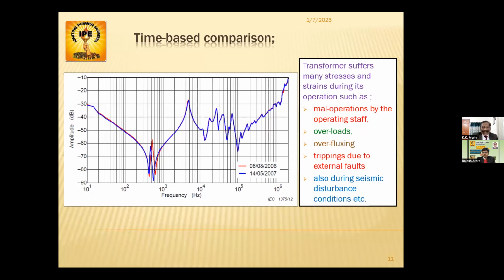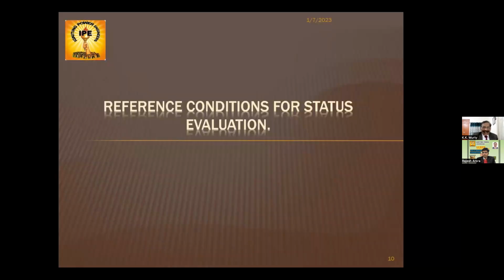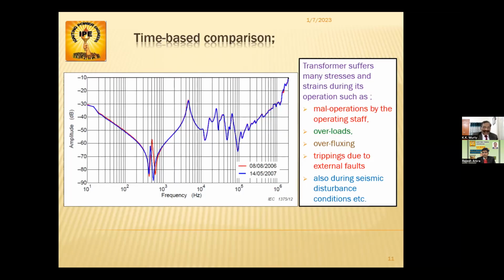So this is the time-based reference condition. The transformer suffers many stresses and strains during operation, such as mal-operation by the operating staff, overloads, overfluxing, tripping due to external faults, and also during seismic disturbance conditions.